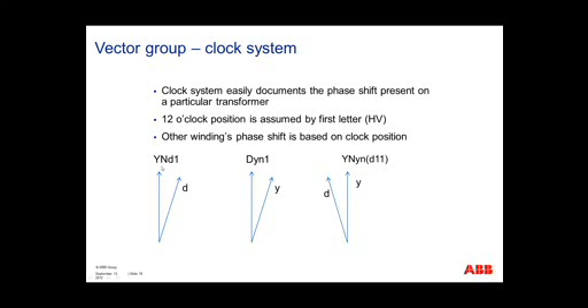So in the first example, we have a YND1 transformer, Y being the Y connection high side of the transformer, and that lays on the 12 o'clock position. The delta, or the low side of the transformer, is at the 1 o'clock position. Here we show the delta at the 1 o'clock position, and we have a separation of 30 degrees, where the high side leads the low side by 30 degrees.